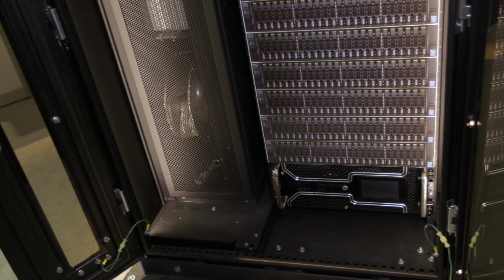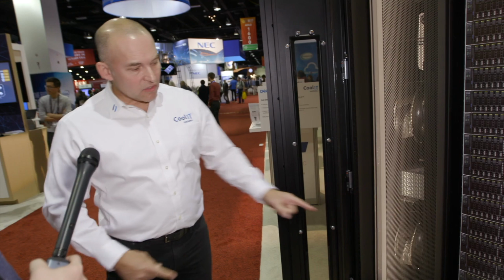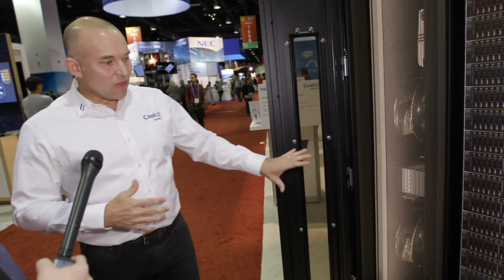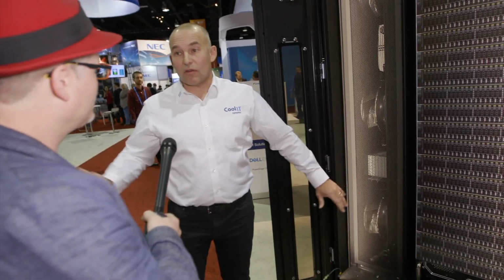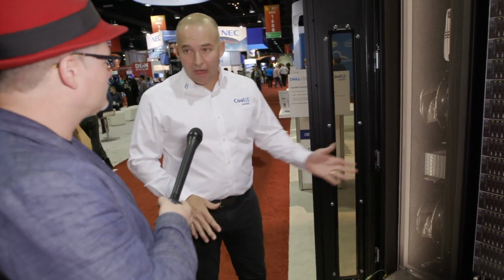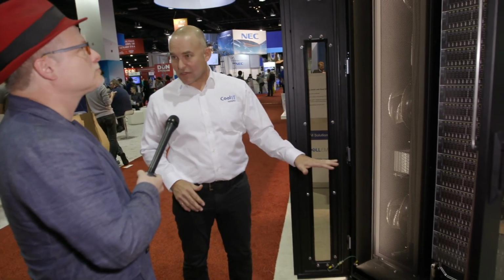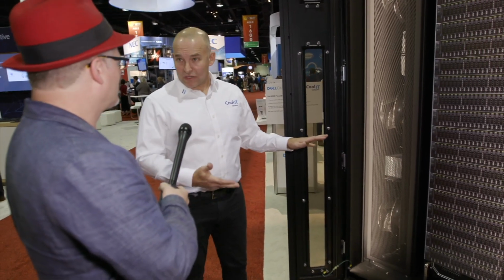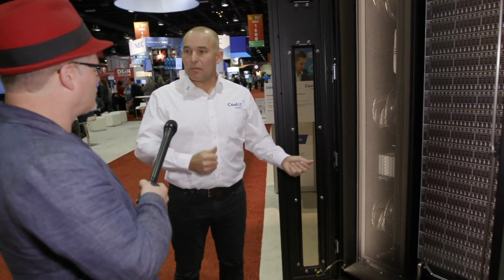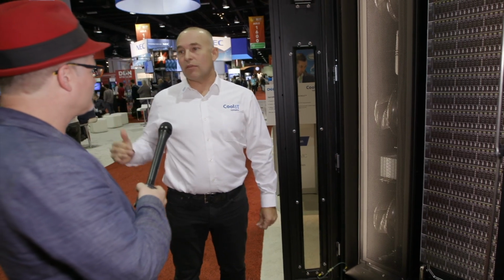So this unit here supplies cool air out to the front. The servers will consume that cool air for the air cooling capacity that's required. Well, in this particular unit, it's a DX unit, so it actually has a condenser, and we have facility water coming in to water cool that condenser. Then the exhaust liquid that comes out of that cycle is what we consume then to cool the direct contact. So even though we could have water coming in at 30 degrees Celsius and then it comes out at 35 or even 38 degrees Celsius, that's no problem for our system since we're doing direct contact liquid. We can accept water all the way up to 45 degrees and keep our direct contact processors perfectly healthy. So we add even more efficiency when we take that exhaust water, raise its temperature even higher, which means that when it returns to the facility, it can then be actually cooled even more efficiently.